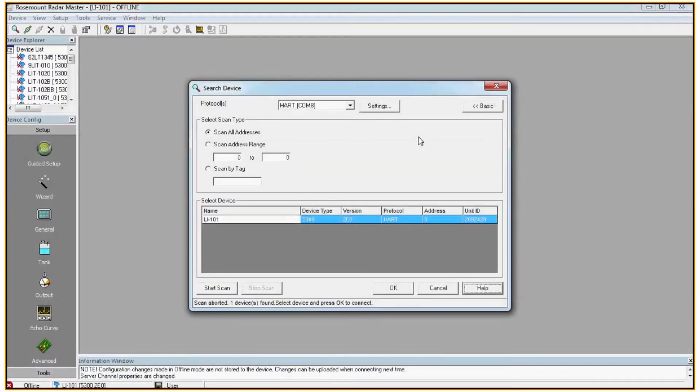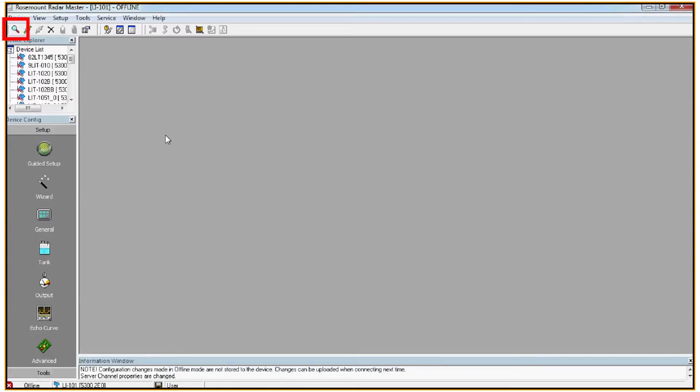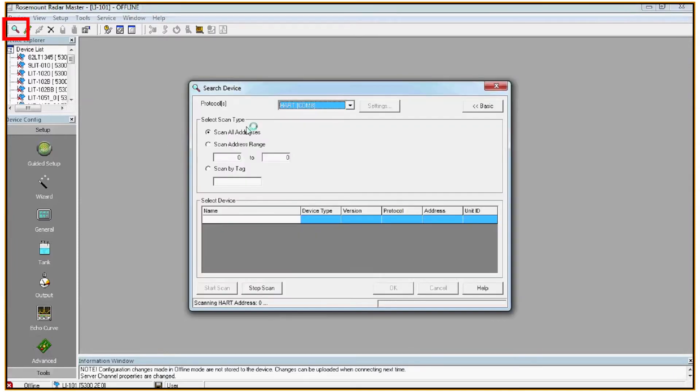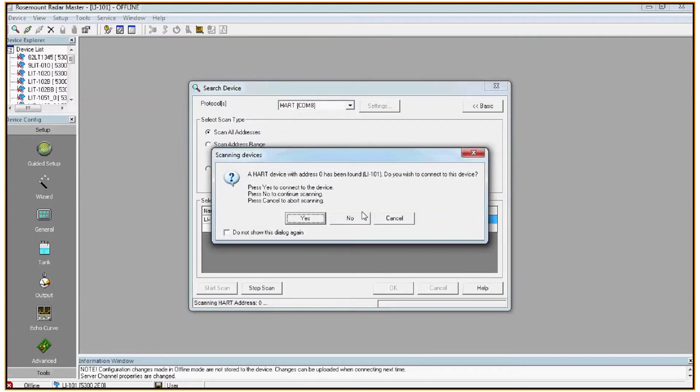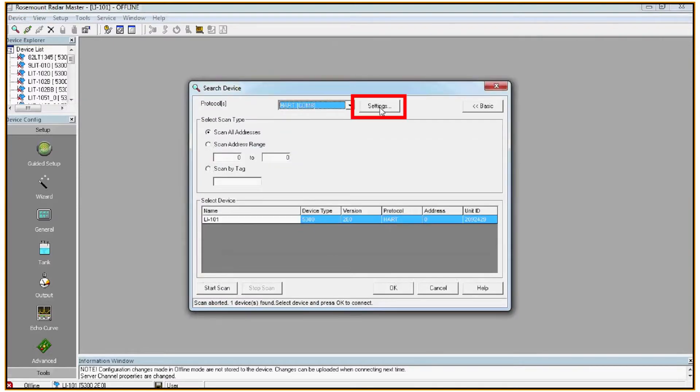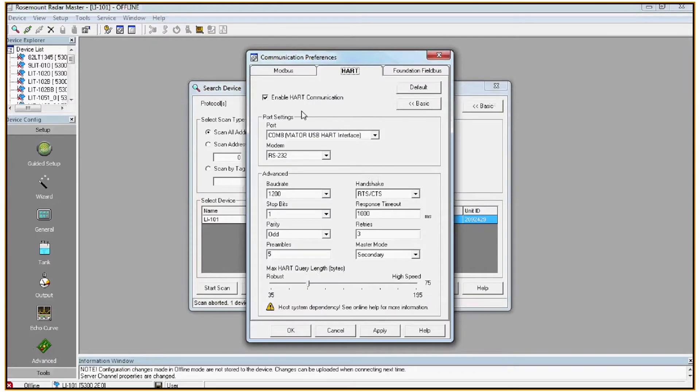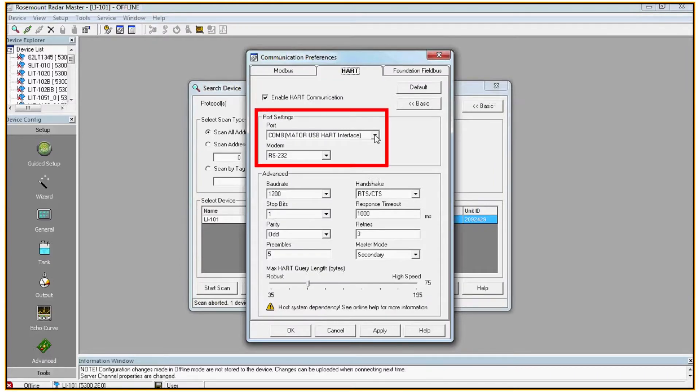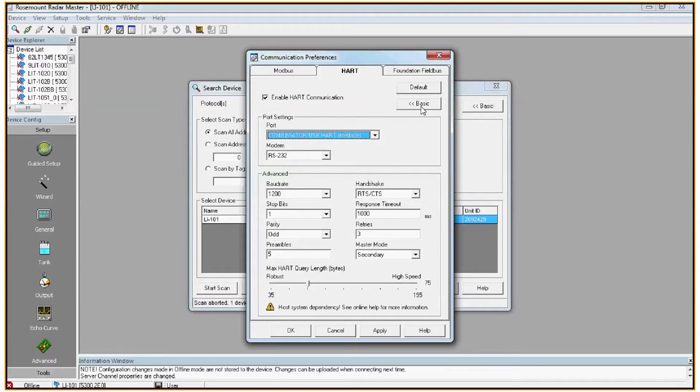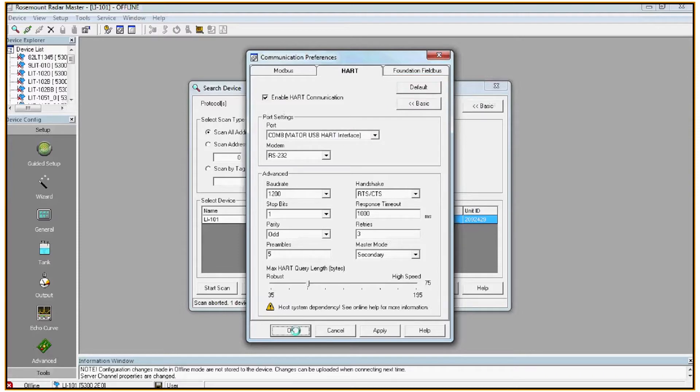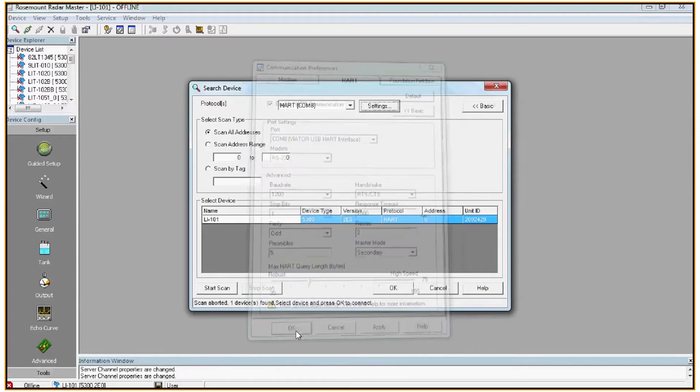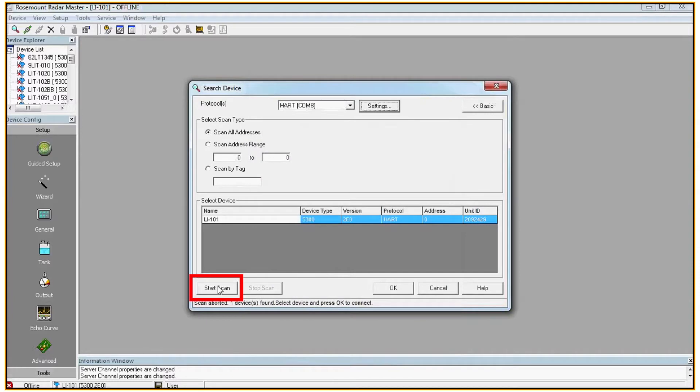When you first open the Rosemount RadarMaster software, you should find that the search device window is open. If it is not, you can simply click in the top left corner on the magnifying glass and it'll pull up the search device window. If you're having issues finding a device, click on settings, make sure that enable HART communications is checked and that the USB HART interface you're using is selected under the port. If you're still having issues, you can click default and set all the protocol settings back to default factory settings. Click OK and start a scan.